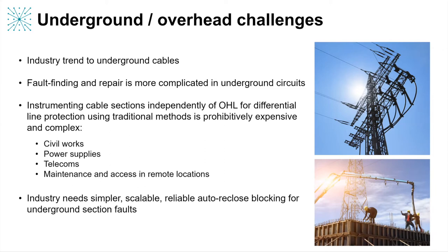Essentially you need to build a substation at any remote measurement location, which then houses the auxiliary power supplies, the digital telecoms and the GPS receivers which underpin that conventional measurement scheme. If you wanted a more cost-effective option with traditional instrumentation, you could use distance protection, but by definition this will only give you an estimate of the fault location as a distance from the substation, which can lead to ambiguity regarding whether the fault is overhead or underground. Because of the risk of auto-reclosing on what might be a permanent underground fault, there is a very strong industry need for a technology that enables cost-effective differential protection on hybrid or multi-section circuits in a way that is simple, scalable and reliable.